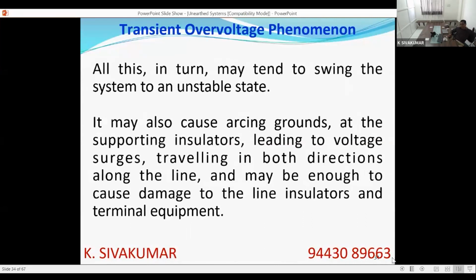Also, this may tend to swing the system to an unstable state. There will be arcing grounds because the voltage to the earth keeps on rising. There will be a tendency for the arc to strike between the phase and the ground or the phase and the earthed conductor. This will lead to the failure of support insulators and the equipment connected to the system, line insulators and terminal equipment. There were reports of failure of equipment, insulators and so on because of this arcing ground.